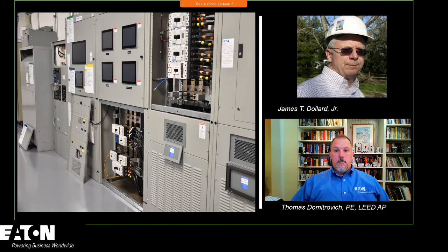And that's why we have seen the industry begin to move in a direction to try to require barriers for years, right? And for decades, actually. We had requirements in Article 408 that said for switchboards and switchgear that were service supplied, we had to have barriers on the line side to prevent inadvertent contact. We probably should have thrown one of those pictures in here, but that's what it was all about. So we added panel boards into that list in Article 408 in 2017. This is just service supplied now. And that's why, if you were to go into any home center, Home Depot or Lowe's, and take a look at the panel boards that are readily available for purchase, you're going to see that they all come with boots for the line side termination.